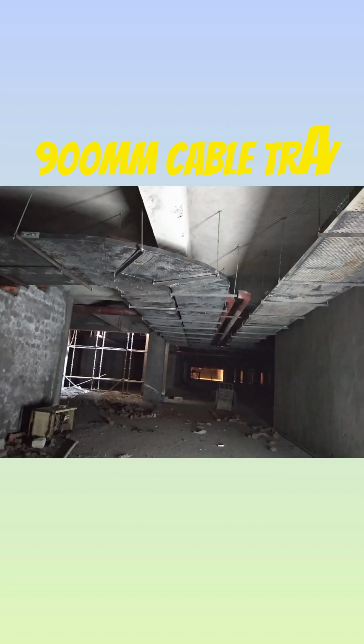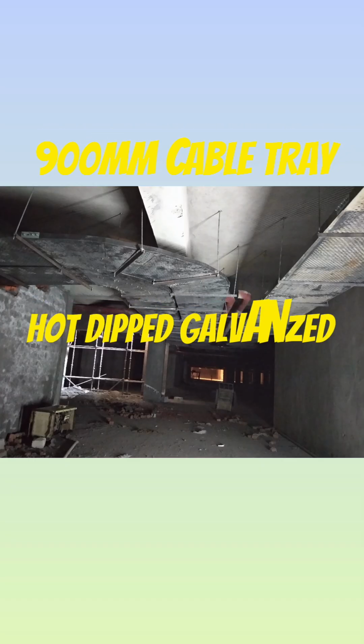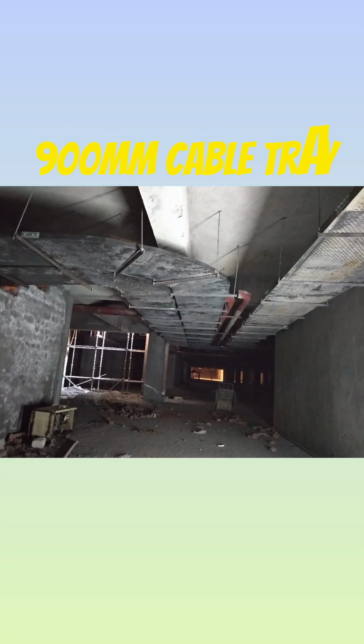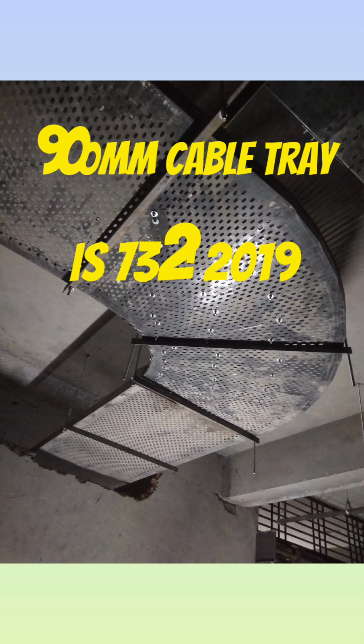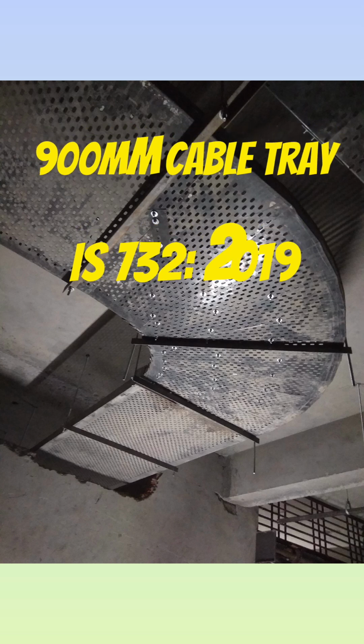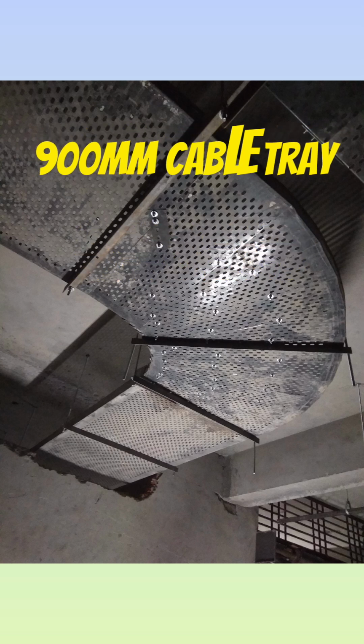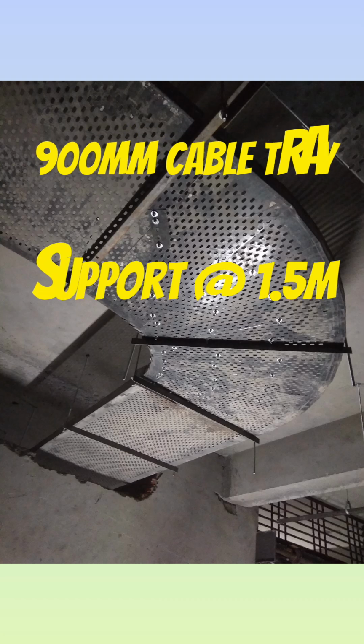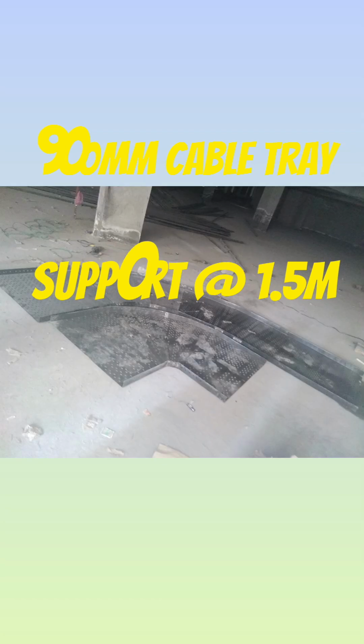The LT room is executed as a dust-proof ventilated enclosure. The primary distribution is via a 900 wide perforated type cable tray. Installation is as per IS 732-2019. Supports are provided at 1.5 meter intervals with additional support at all bends and tees. The entire tray system is electrically continuous and bonded to the main earth grid at 20 meter intervals using 25 by 3 GI strip.